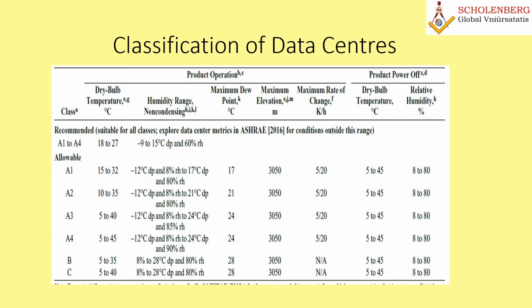As you could see clearly from this table, the recommended dry bulb temperatures, humidity ranges, maximum dew point, maximum elevation allowed, maximum rate of change are clearly given here, and dry bulb temperature and relative humidity are mentioned for each and every class here. Well, here if you see the recommended, that is suitable, dry bulb temperature ranges are mentioned here for A1 to A4. We have already seen what class A1, class A2, and class A4 are, but for most of the industrial data center applications, you may be finding only the A1. So for the A1, the recommended dry bulb temperature by ASHRAE is between 18 degrees Celsius to 27 degrees Celsius. Here the humidity range also you may find that up to 60 percent relative humidity is allowed.